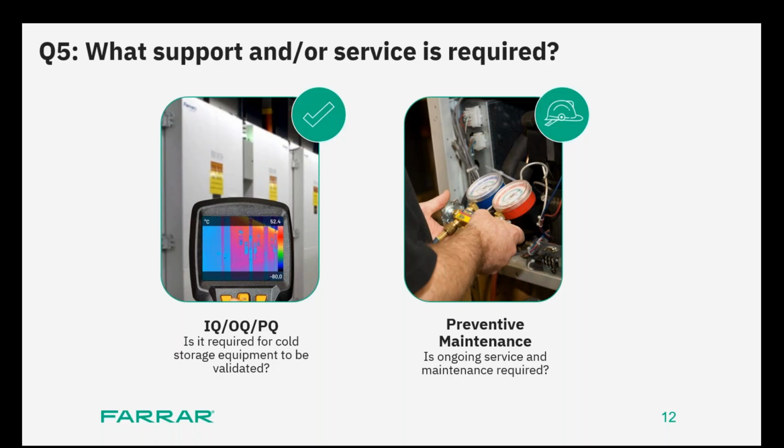Then when you go into the PQ, which is your performance qualification, if you have simulated product in there, things of that nature, we are going to show you that we are creating and you're having the results that you need. So this ensures and safeguards everything that you're putting into your chambers. So you're guaranteed that your investment is working right, and you are safely understanding and knowing and sleeping at night that your product is stored properly in there.